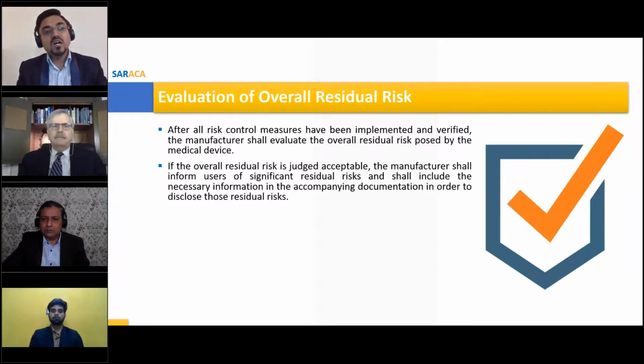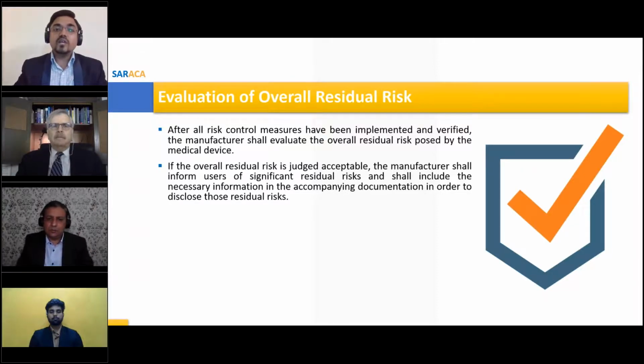So how can you evaluate those overall residual risks which are associated with your medical device, and what will you do once you have estimated the overall residual risks? After implementing all risk control measures, once you implemented and verified all the risk control measures and all are in place, you have minimized, controlled or mitigated the risks as far as possible. But then you need to evaluate.